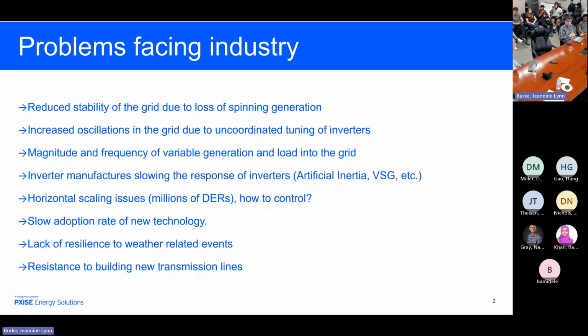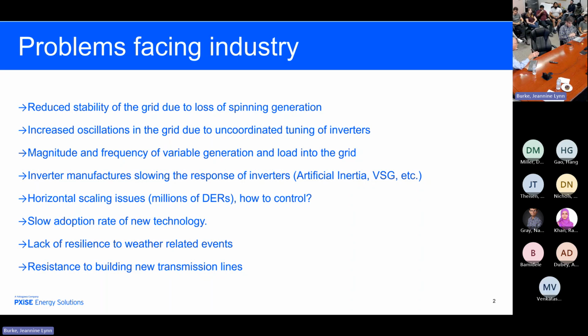We don't know that for sure, but it also can be due to the fact that we're losing inertia in the grid. The grid then is more sensitive to disturbances. The disturbances are coming from uncontrolled DERs. They're causing the RLC part of the grid to be more predominant than it is today. When it's massively damped by large generation, we don't see this higher frequency oscillation. So these harmonic frequencies are probably going to get more important in the grid. So we need to find a solution for them.